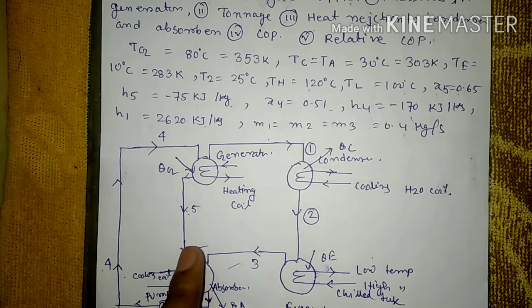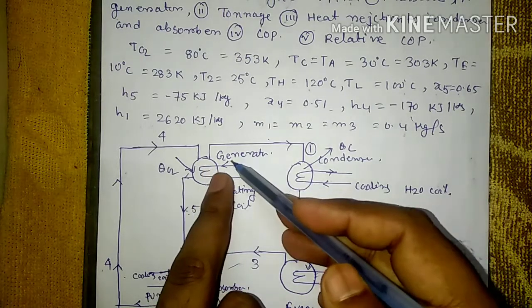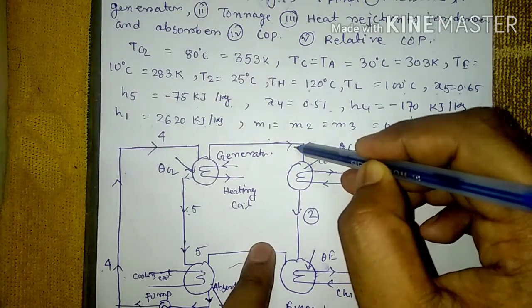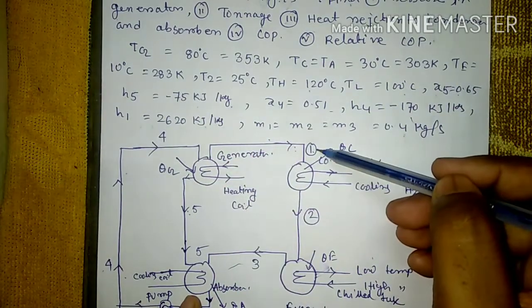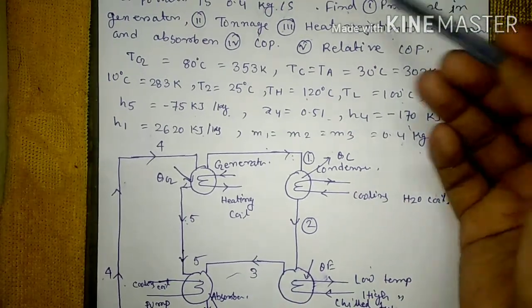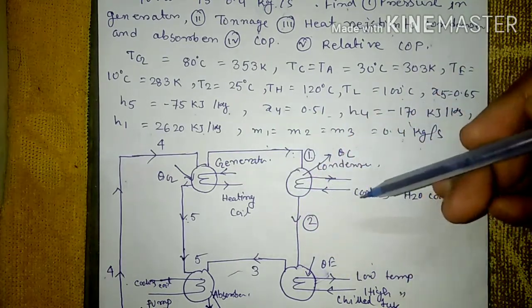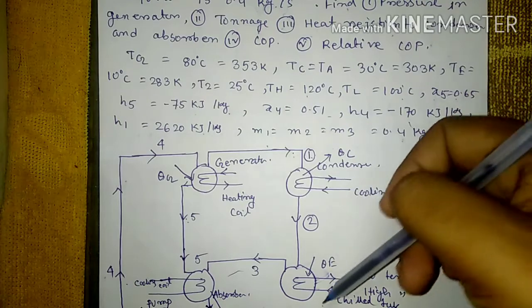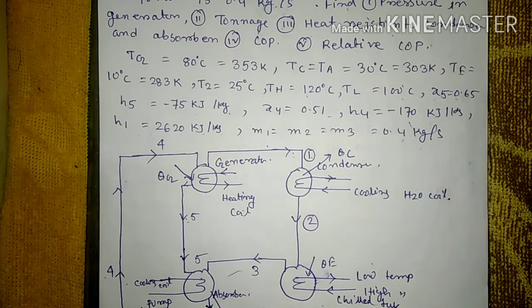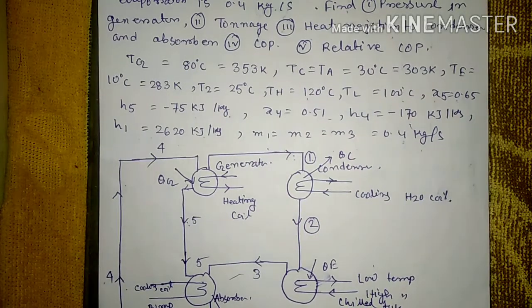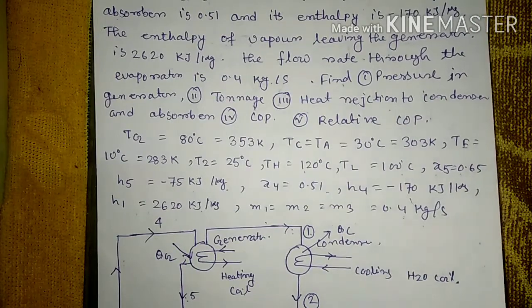The enthalpy of vapor leaving the generator is h1 = 2620 kJ/kg, and the mass flow rates through the evaporator are m1 = m2 = m3 = 0.4 kg/s. We need to calculate pressures in the generator, condenser, evaporator, and absorber; tonnage or cooling capacity; heat rejection to the condenser and absorber; and the COP.